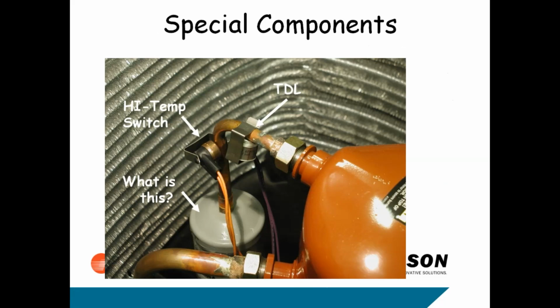Some other things on the two-step scrolls, you've got some other components. There's a temperature control for the crankcase heater. There's a high temperature switch to shut it off if the discharge gets too warm. And the little container there that says, "What is this?" That's not a dryer, that's a muffler, okay? The reason I talk about that is because I have had guys in the field think that was a dryer, and when they put the compressor in, they put a dryer in there. Dryers do not do well in the discharge of the compressor. They belong in the liquid line after the condenser.